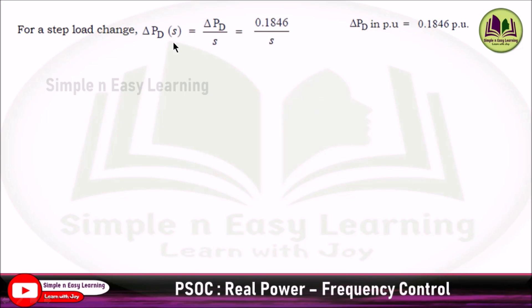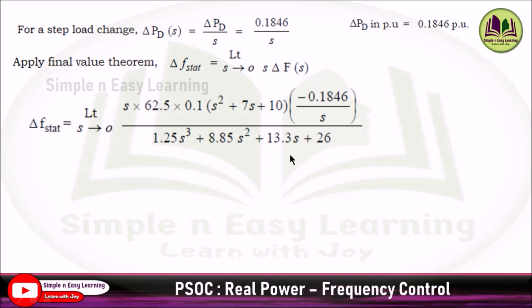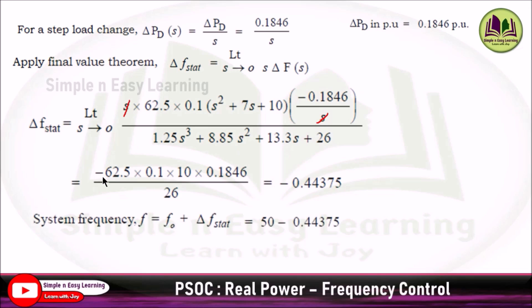For a step load change, ΔPd(s) equals ΔPd divided by s, which is 0.1846 divided by s. Applying the final value theorem, Δf_stat equals limit s tends to 0, s times Δf(s). Substituting the whole expression, multiplying with s, we can cancel out this s. Substituting s equals 0, the equation gives minus 0.44375 as the answer for steady state frequency variation. The system frequency changes according to this, so f₀ plus Δf_stat, 50 minus 0.44375, gives 49.5562 hertz.